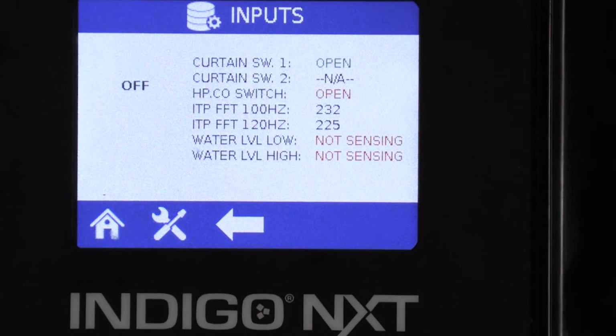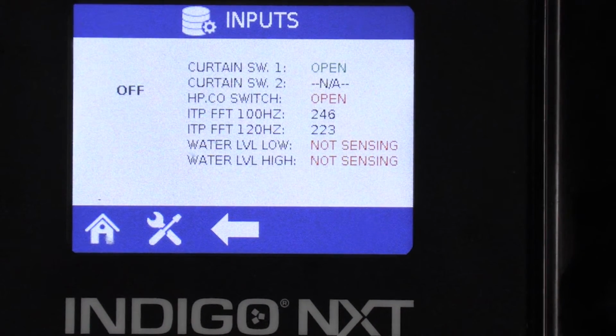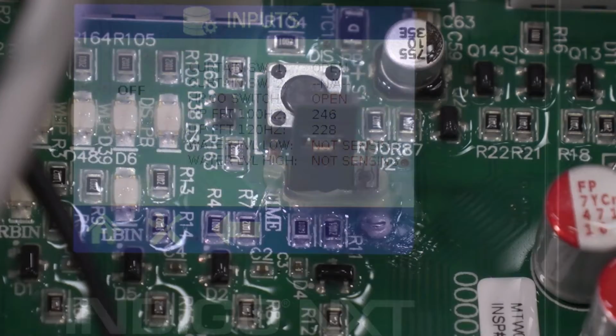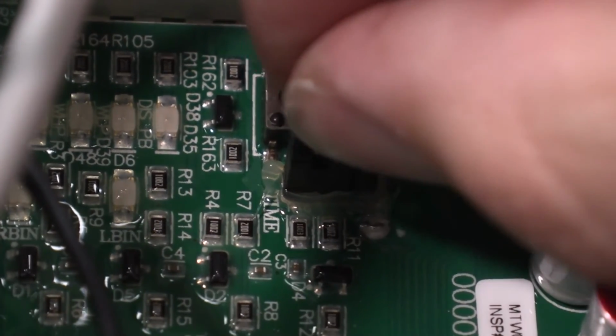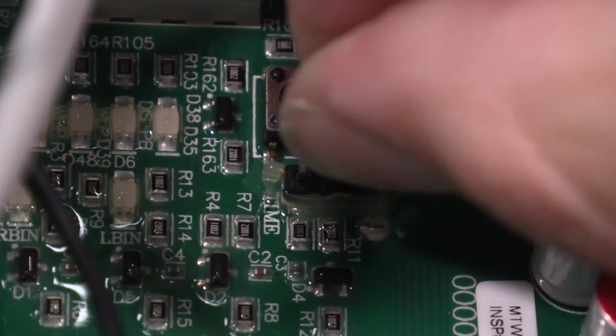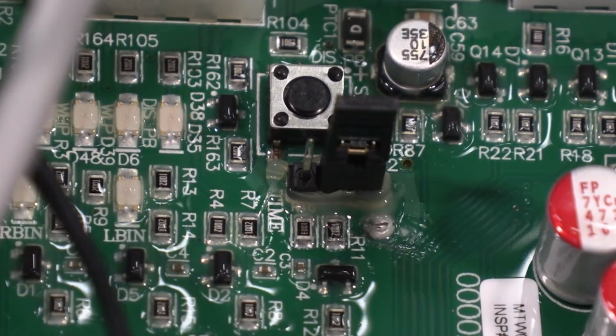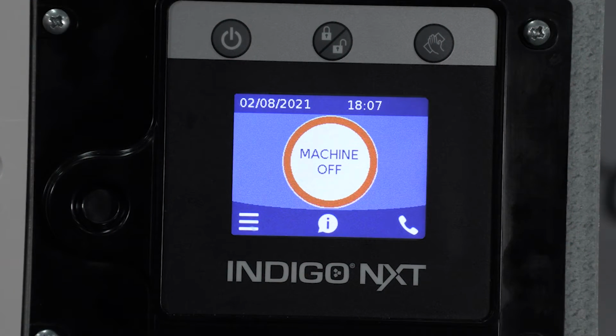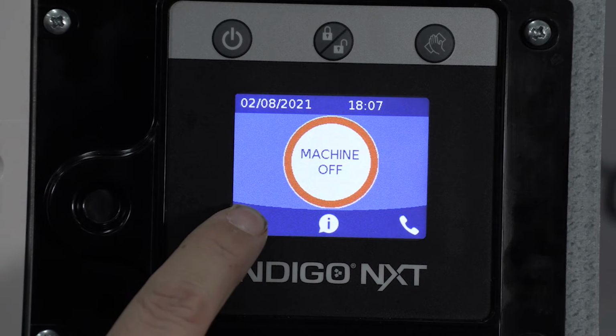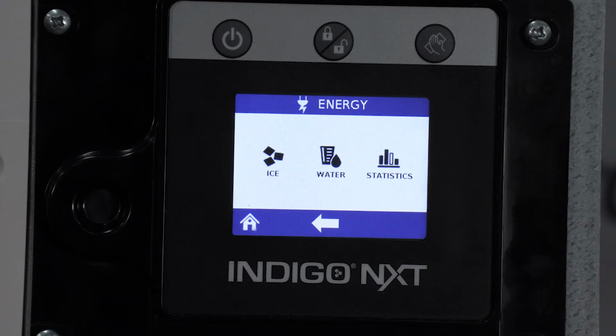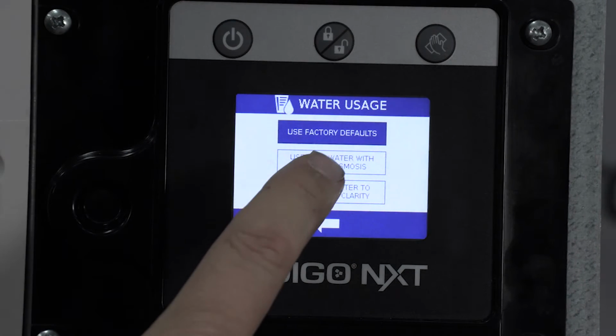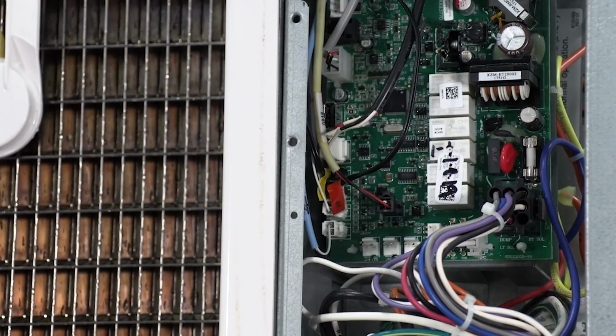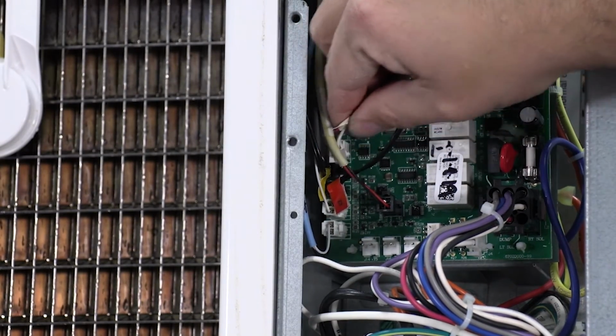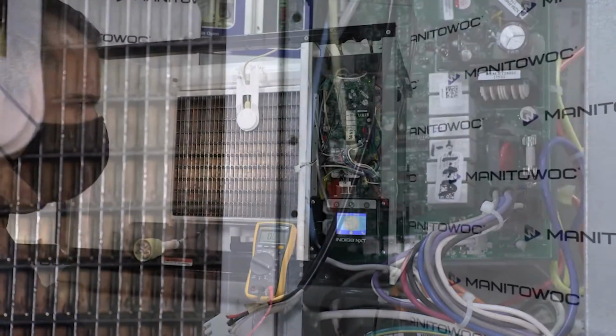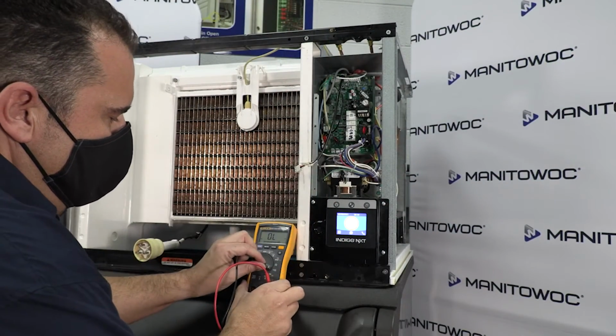If water level probes are touching water in the water trough and the display is reading not sensing, then continue with Step 4. If using RO or deionized water, increase the sensitivity by moving the TDS jumper over 1 pin on the control board as shown. Then enable the RO menu by navigating to the menu, Energy, Water, and then select Use Less Water with Reverse Osmosis. Step 4. Disconnect the water level probe wiring harness from the control board and ohm out the water level probe while connected to the wiring harness.